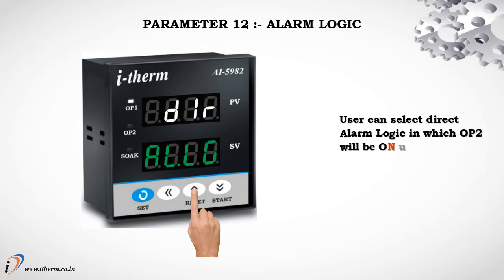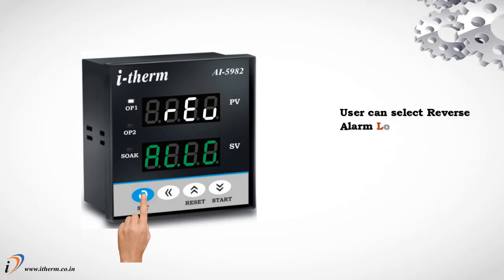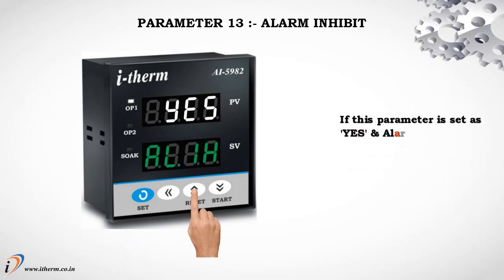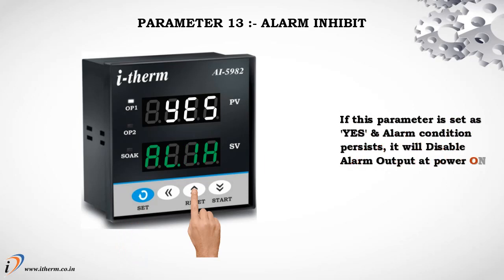Parameter 12: Alarm Logic. The user can select direct alarm logic, in which output 2 will be on under alarm condition, otherwise off. Parameter 13: Alarm Inhibit. If this parameter is set to Yes and an alarm condition persists, it will disable the alarm output at power on.